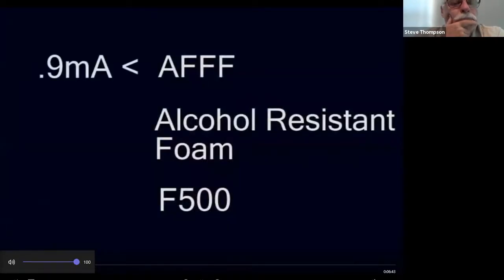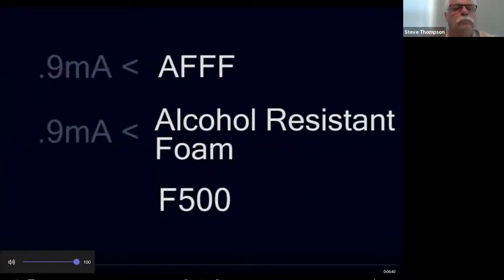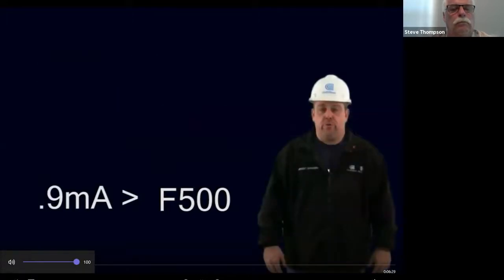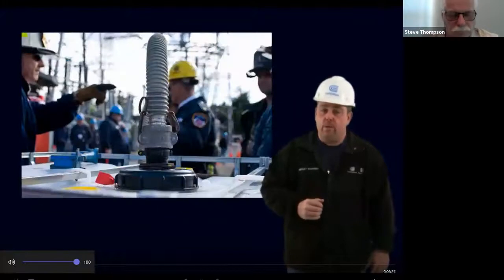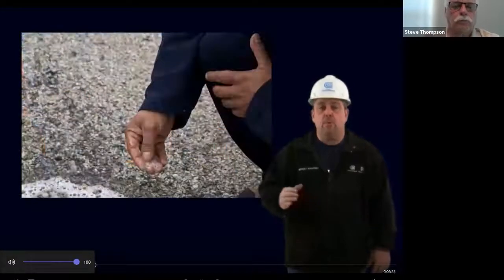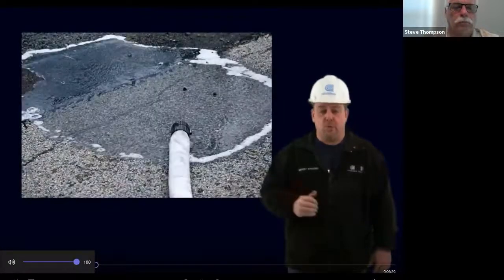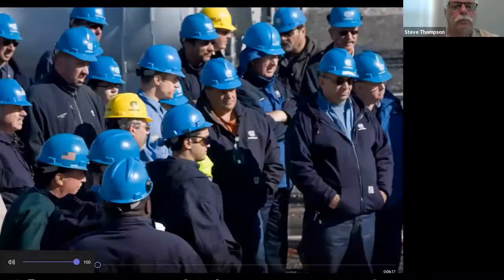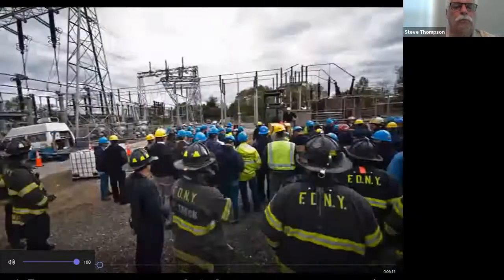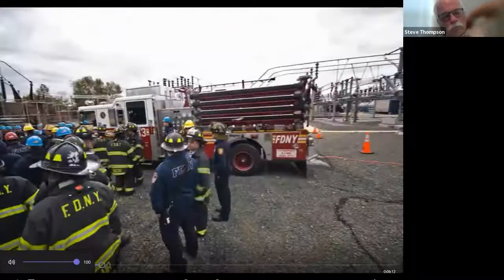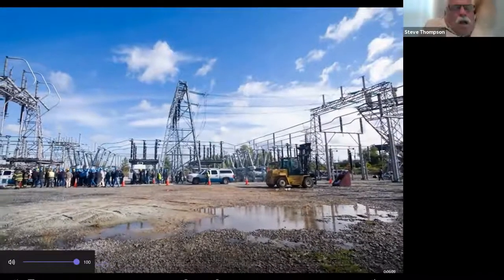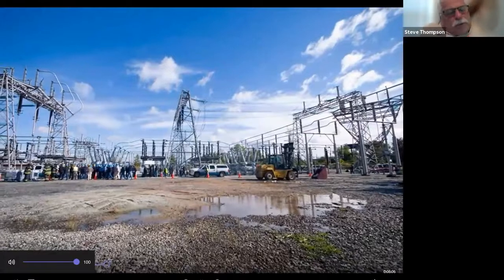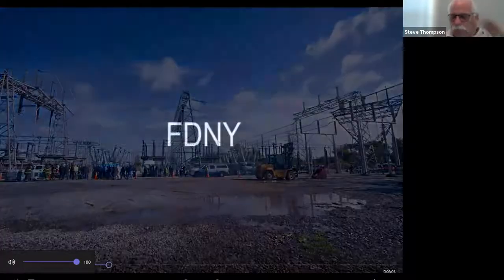The current leakage values from the AFFF and alcohol-resistant foam exceeded the established safety limit of 0.9 milliamps, but the F500 agent produced leakage values similar to that of water, which we already knew to be safe. F500 does not fall into the category of traditional foam. It is considered an encapsulating agent capable of providing quick knockdown coupled with heat dissipation. These promising test results enabled us to move forward and conduct a live field test at the Fresh Kills substation. The selection of this site was driven by our need to conduct the testing on the highest voltage that the fire department could reasonably encounter.